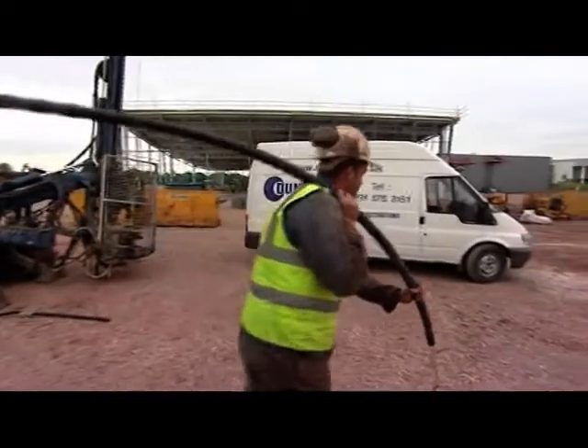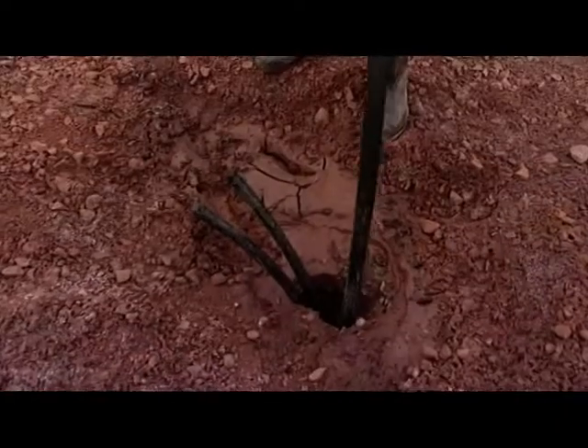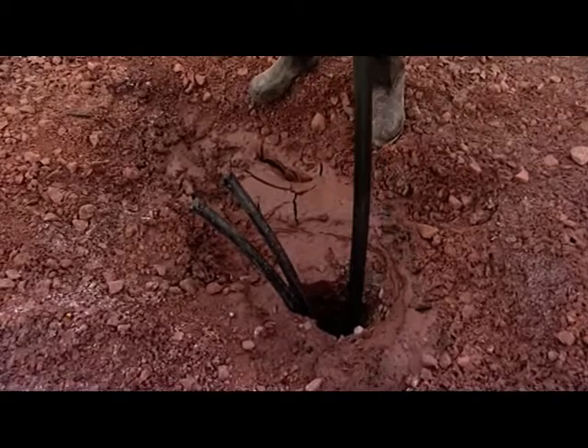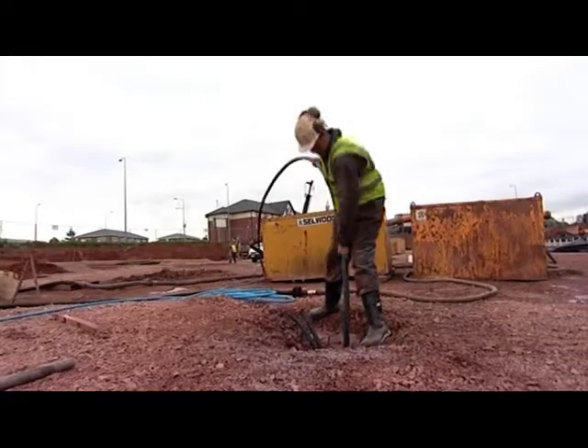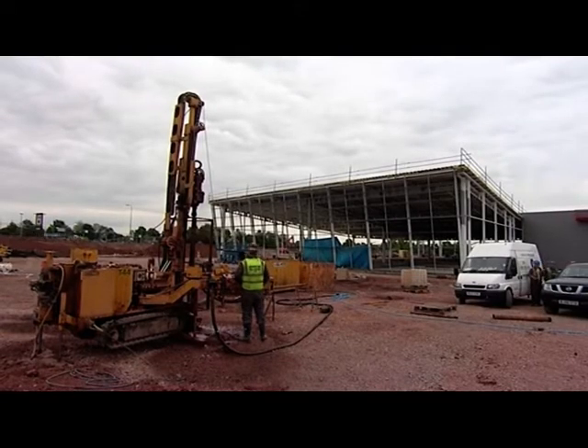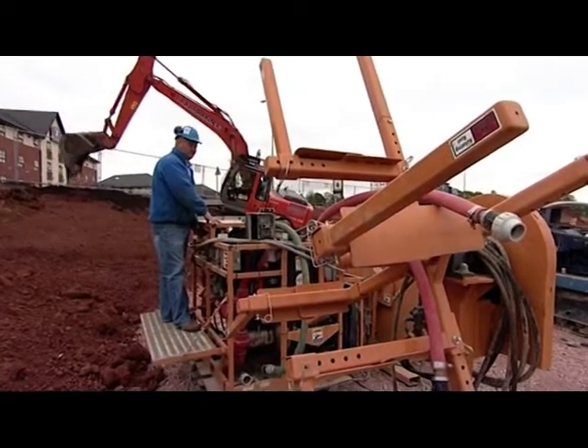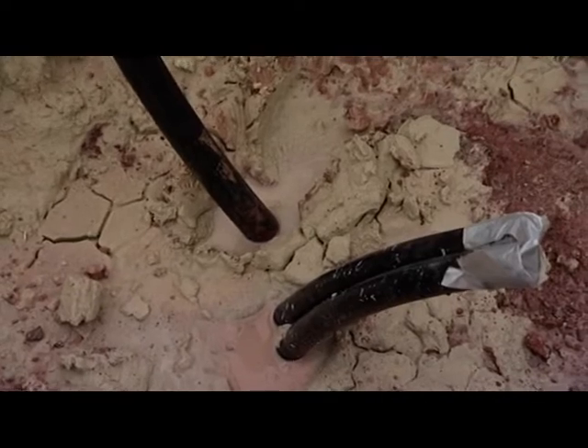The polyethylene loops going down into the boreholes will eventually all be linked up. Once they've been flow tested and pressure tested, these pipes will carry what's called a heat recovery fluid — a glycol and water mix that only needs to absorb a small amount of energy in order to see a rise in its temperature. The beauty about boreholes is that below 15 metres deep the temperature of the ground is very stable all year round, staying at around 13 or 14 degrees C. That temperature is enough to raise the temperature of the liquid by only 3 degrees C, and what that enables us to do is to pump the heat recovery fluid through pipes into the ground so it absorbs energy from the ground.